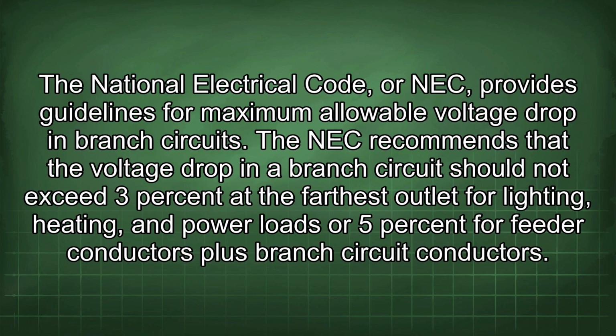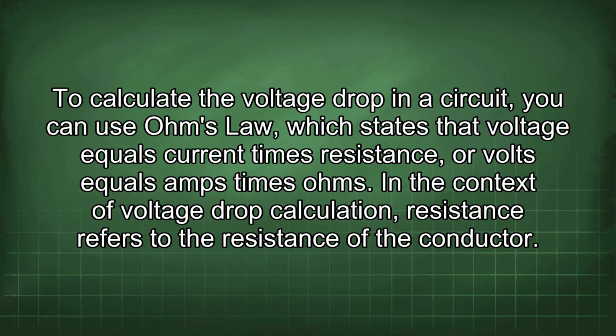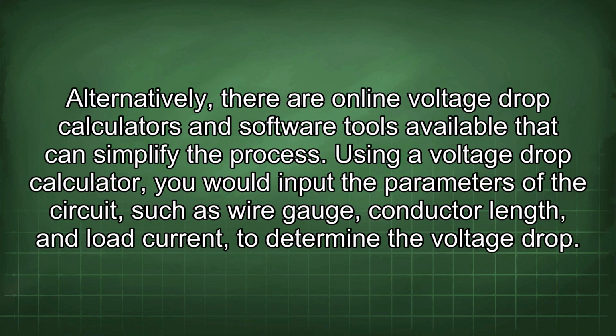The National Electrical Code, or NEC, provides guidelines for maximum allowable voltage drop in branch circuits. The NEC recommends that the voltage drop in a branch circuit should not exceed 3% at the farthest outlet for lighting, heating, and power loads, or 5% for feeder conductors plus branch circuit conductors. To calculate the voltage drop in a circuit, you can use Ohm's law, which states that voltage equals current times resistance, or volts equals amps times ohms. In the context of voltage drop calculation, resistance refers to the resistance of the conductor. Alternatively, there are online voltage drop calculators and software tools available that can simplify the process. Using a voltage drop calculator, you would input the parameters of the circuit, such as wire gauge, conductor length, and load current, to determine the voltage drop.